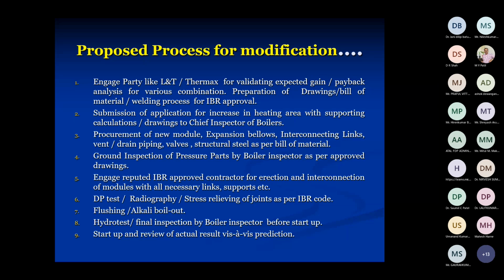Then comes the procurement of the new module. We have to give the fabrication design to another company who can fabricate the module for us. Then expansion bellows, interconnecting links, vent and drain pipings, different types of valves. Then there will be a change in the structure also; we have to calculate the structural steel, take it on the drawing, and prepare the bill of material. Now all these parts are of IBR quality, so they are to be inspected by the chief inspector. So before going into fabrication, the ground inspection of all the pressure parts by the boiler inspector as per approved drawing was carried out.